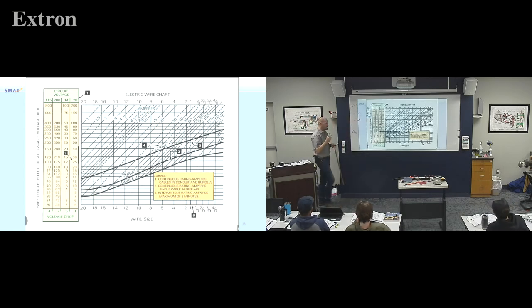It was a 2-step process. One was get the one you think you want to use, but then backtrack to your amperage, and wherever you hit the curve of what you were, you could drop down the line. So if it was intermittent use, not in a bundle, that one was all the way out here, and you'd go, okay, we're still good, I'd use the 12. So if you want to play around with that one, you can.